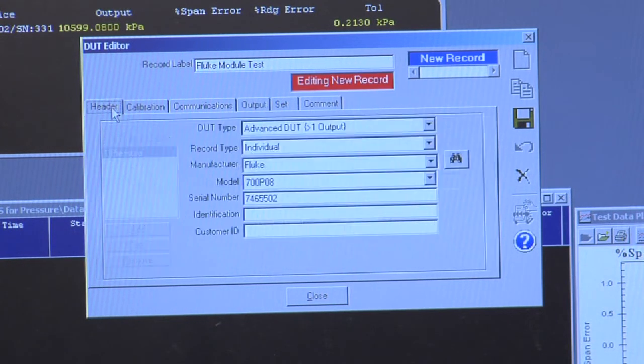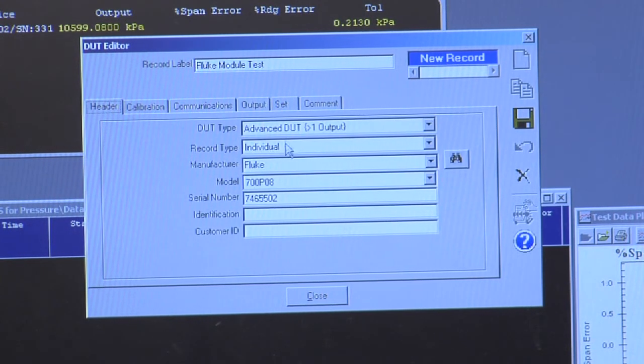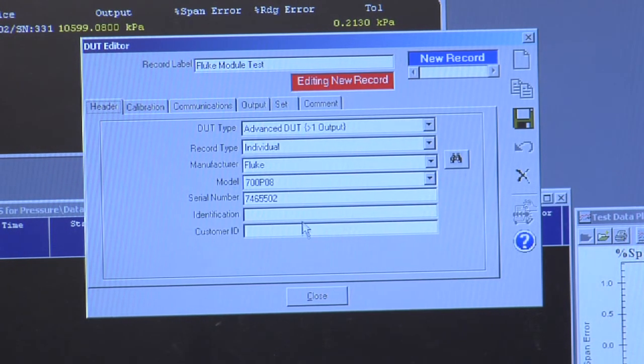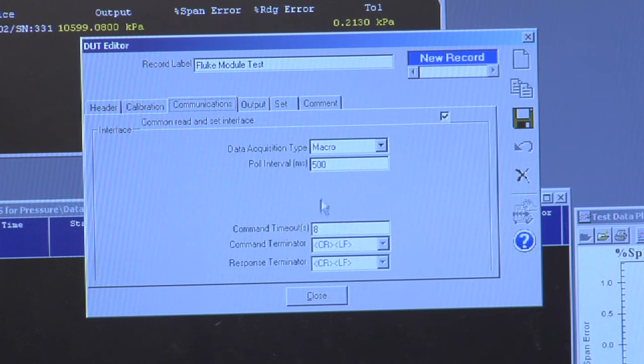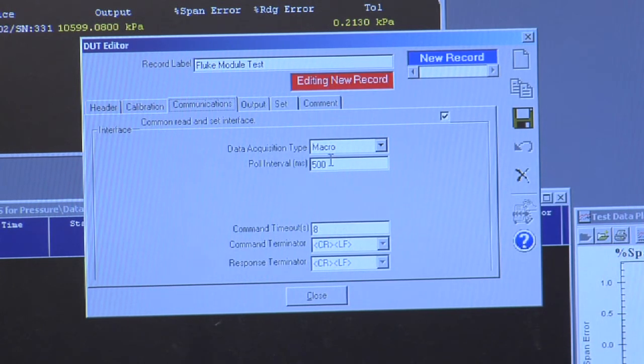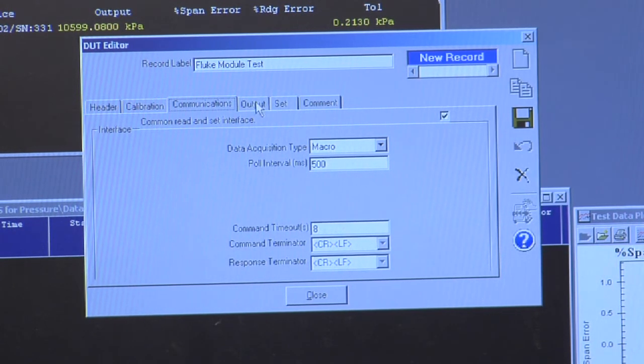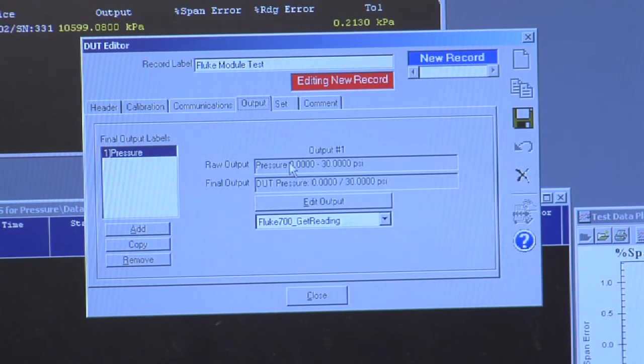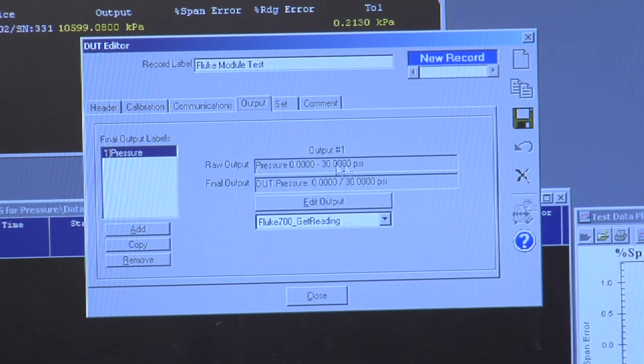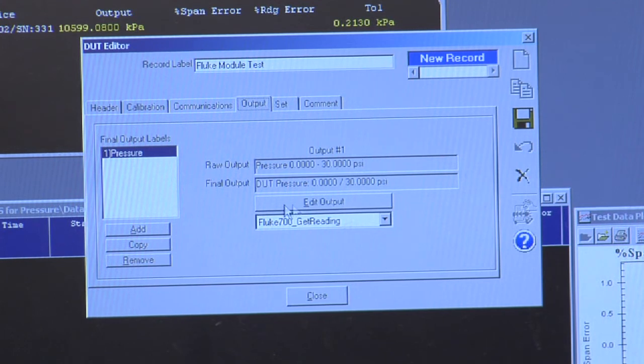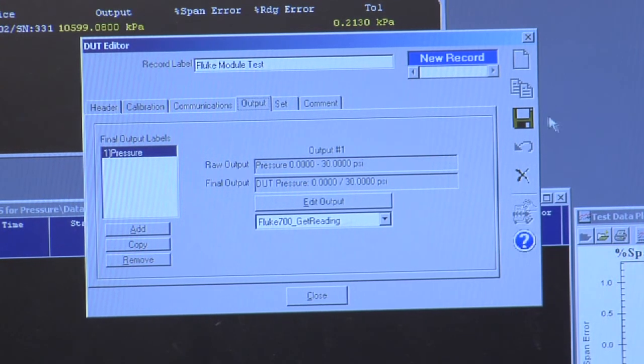So I have identified the instrument. I've defined how I'm going to communicate with it. I've defined its output range. So in this case, it's 30 psi. And it's going to use this specific macro.